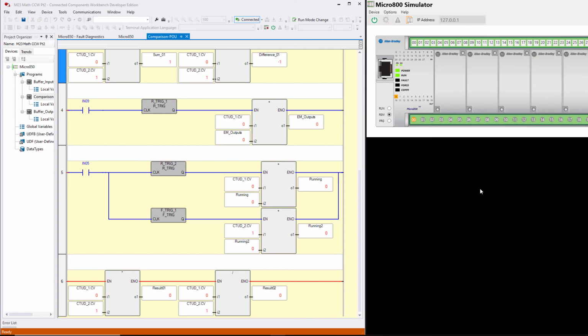Okay, so now here we are with our multiply and divide, and we're not faulting. Now, hopefully none of this confused you, but you can't divide by 0. Not on pencil and paper, and especially not in a computer. I did talk about the data overflow in the manual, that for a double integer has a range of minus 2147483648 to a plus 2147483647. And the reason this overflow happened is because you can multiply by 0, but you can't divide by 0.